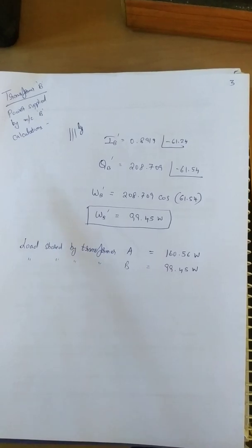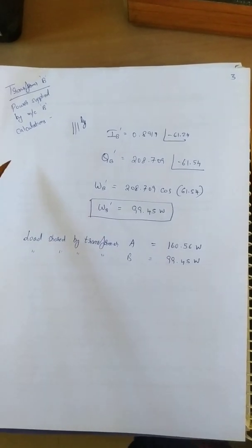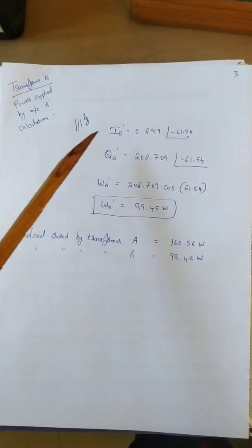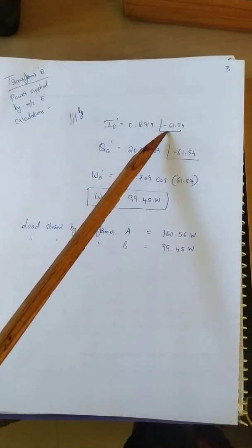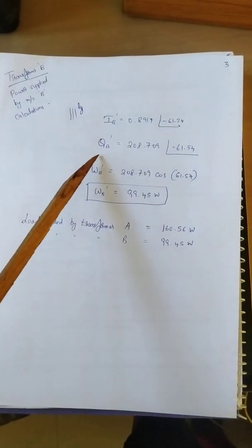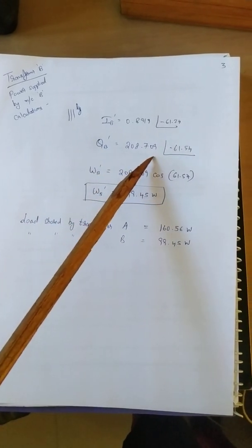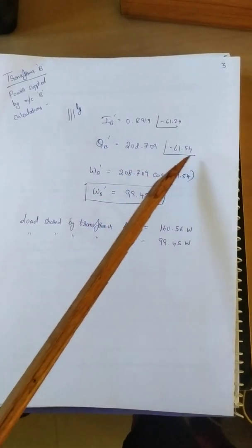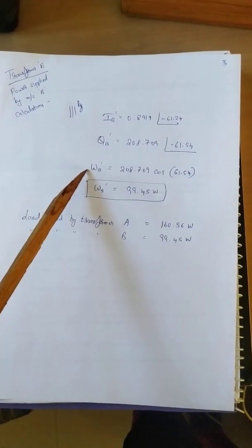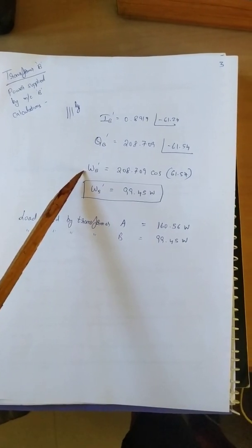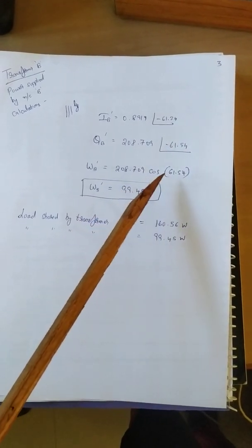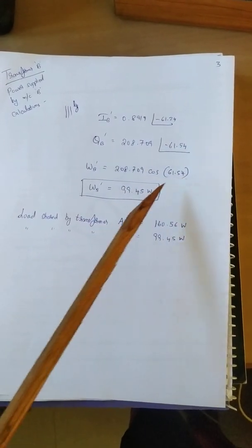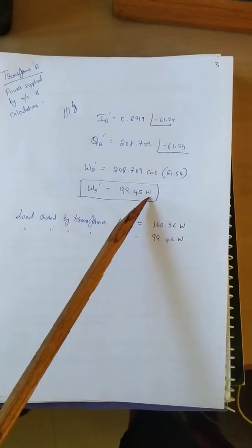Similarly we calculate the power supplied by machine B or Transformer B. We have IB dash is equal to 0.8919 at an angle minus 61.24. We get kVA, QB dash 208.709 at an angle minus 61.54. And we get WB dash which is the power supplied, which is kVA multiplied by cos phi, is 208.709 into cos of 61.54 which is 99.45 watts.